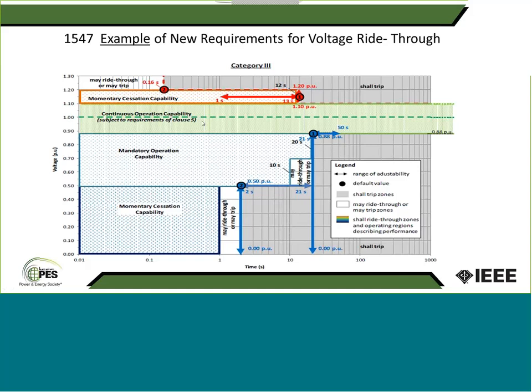It's like a continuous ride-through requirement, so the continuous operation of the DER. So if the voltage is between 110% to 88%, the DER will remain connected and produce power. The mandatory operation, the concept is similar, and the only difference is there's a limited time for that mandatory operation.